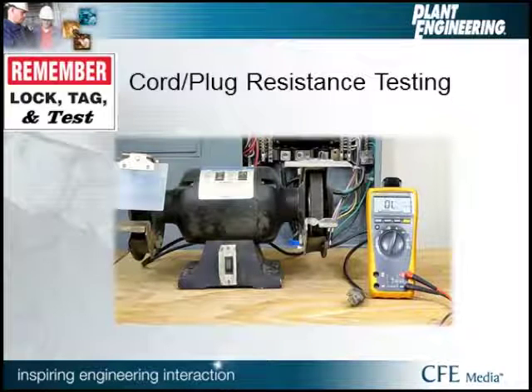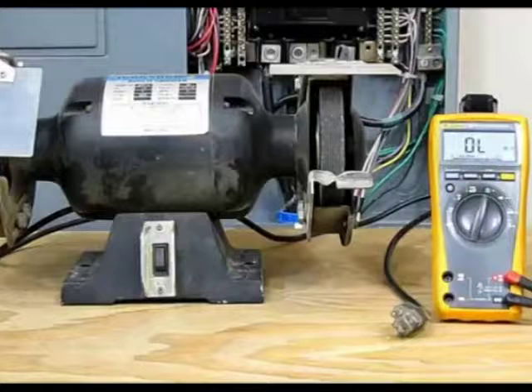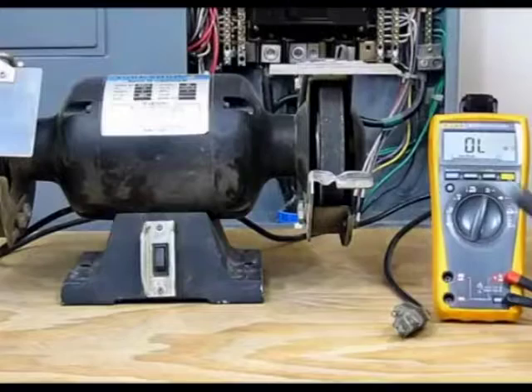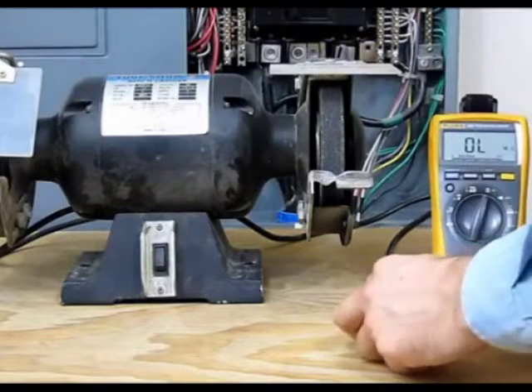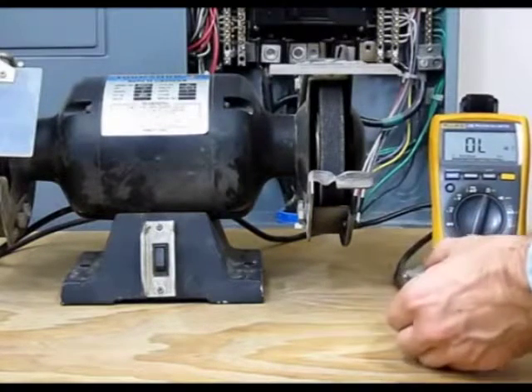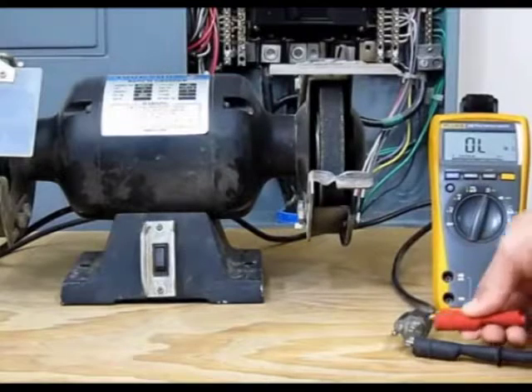And our final resistance test will be done on a cord and plug piece of equipment. This test is being performed to check the windings on a single-phase motor. However, this motor is part of a cord and plug tool, so we will be performing the test through the cord.